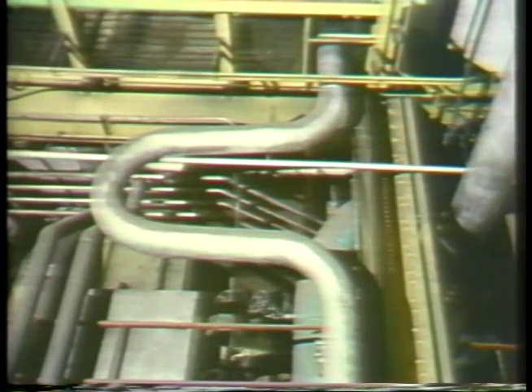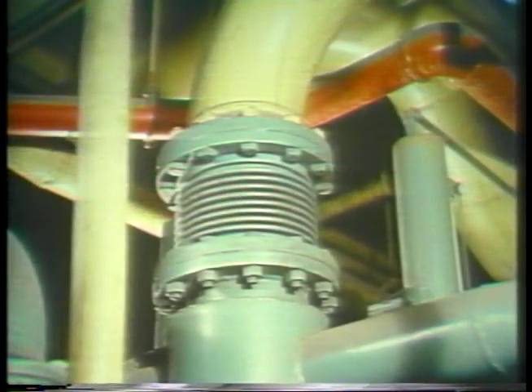Expansion loops are used in steam lines to allow the steam pipe to expand as it heats up without breaking. If the pipe did not have room to expand, stress on the pipe would increase, and it could break. A second way of providing for expansion and contraction of pipes is to put an expansion joint in the pipe. This is one type of expansion joint.